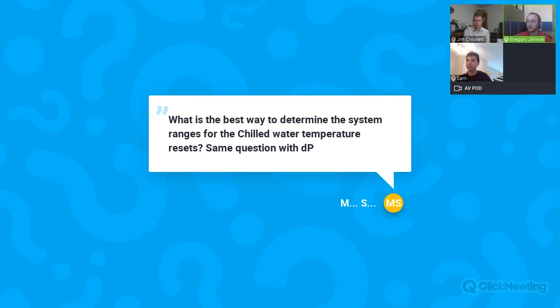The biggest problem there is that a lot of times they just run there all the time. So putting in the reset allows you to back off when you don't necessarily need to be there all the time. So let's just say 42 degrees is probably a safe number to go for the bottom end. I wouldn't necessarily say you really need more than that. Even for mechanical dehumidification needs, there's kind of diminishing returns beyond 42 degrees. Unless you've got some really extreme conditions that you need to maintain in like a clean room or something like that, that's maybe extenuating circumstances. But even in hospitals, they have ORs that have pretty tight requirements. 42 degrees really is probably all you need.